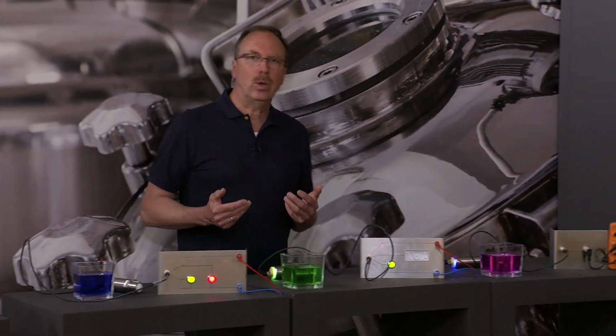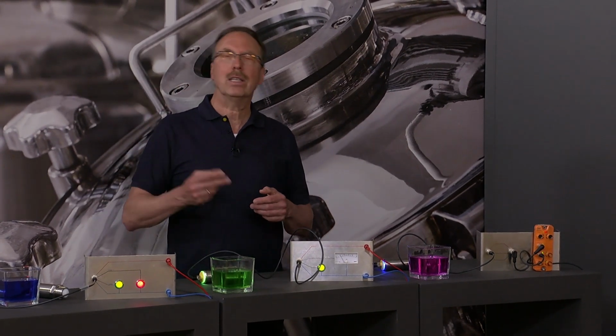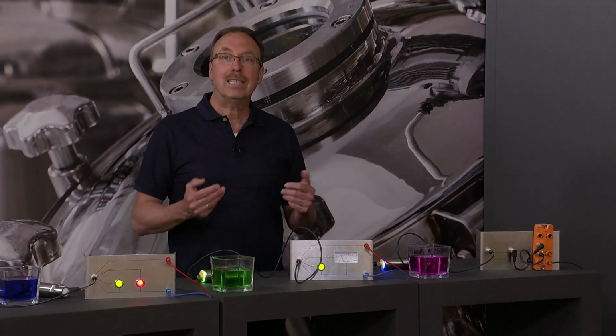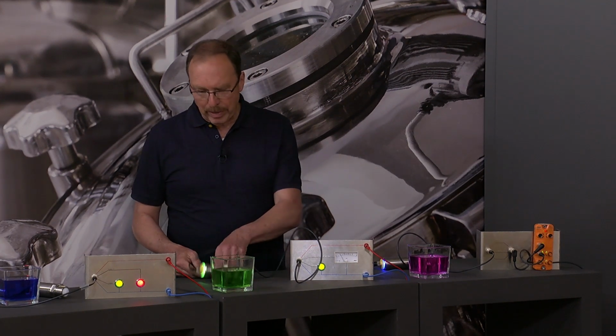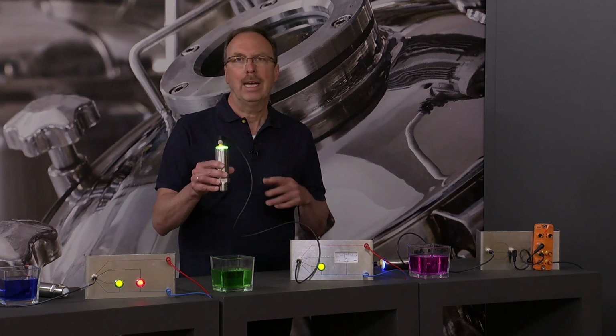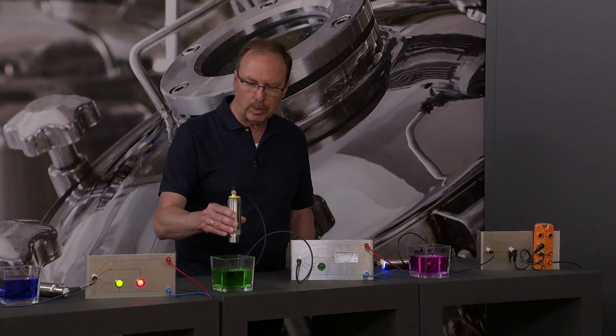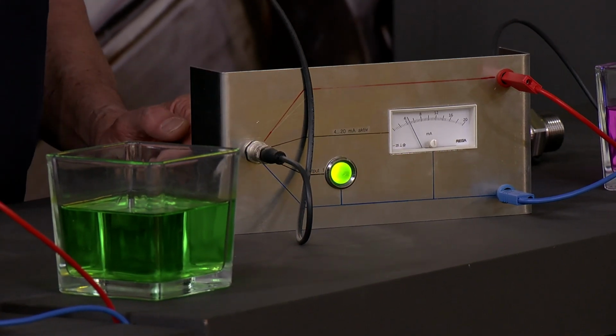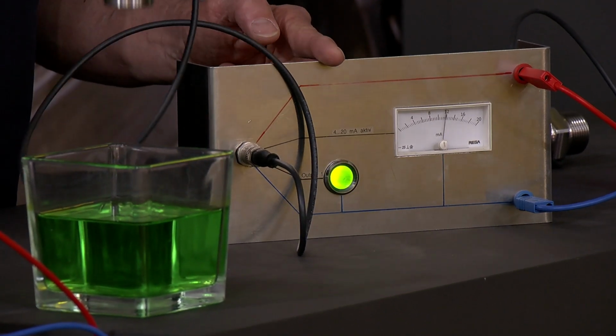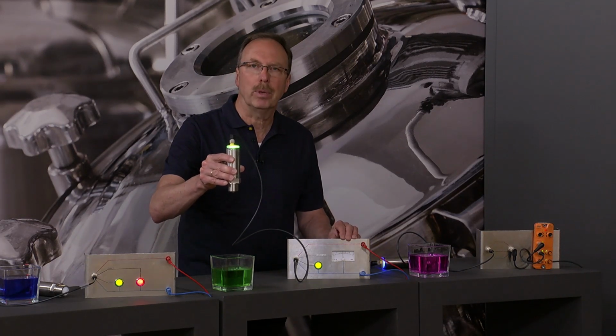With the same electronic, it's possible to use, instead of 2 transistor outputs, the second transistor output as a current output, as a 4 to 20 milliamp active current output. So here we have used the same sensor with the same electronic, just a different adjustment, and we can use the similar demonstration. On the light ring, we have this difference here, but we have also the transistor output. But also, in addition, we have the analog output of the instrument.